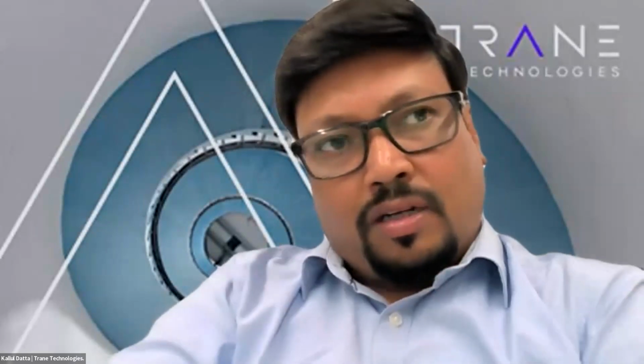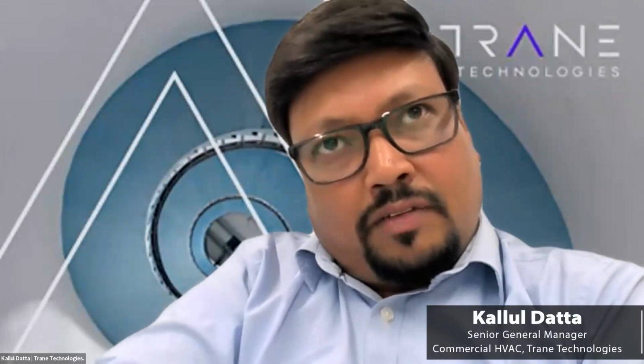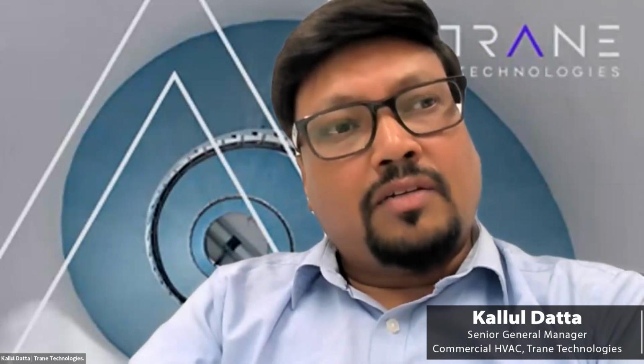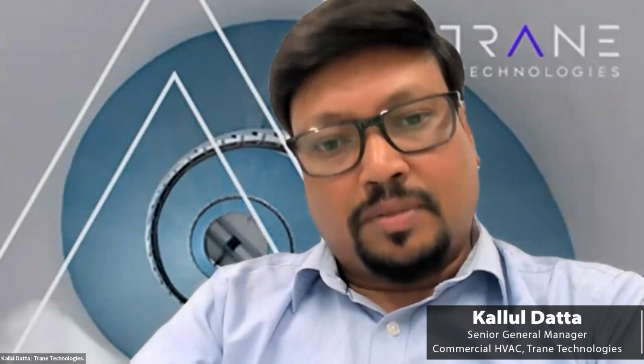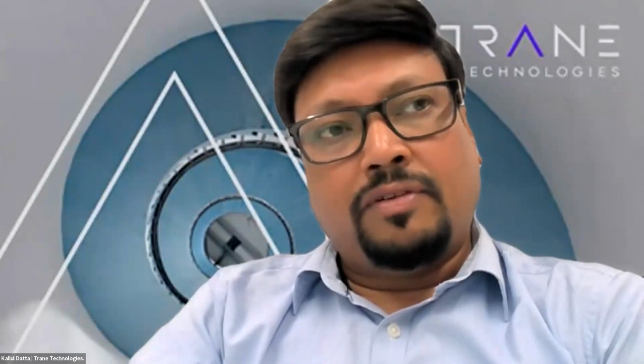Mr. Datta, there was a question for you also. What ambient temperature can we use for the free cooling option? Thank you, Mr. Gopal. In free cooling, currently with modern generation chillers, as I explained in this presentation, we can start free cooling depending on the return water temperature the chiller has been designed for, and what the chilled water requirement is in the data loop. For example, if a data center is designed for 27 degree chilled water leaving and 37 degree return.